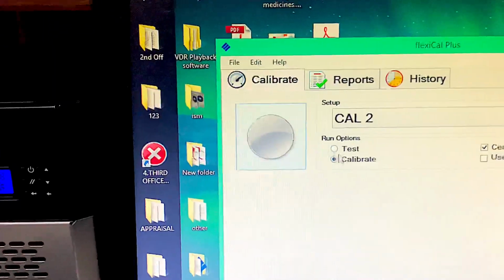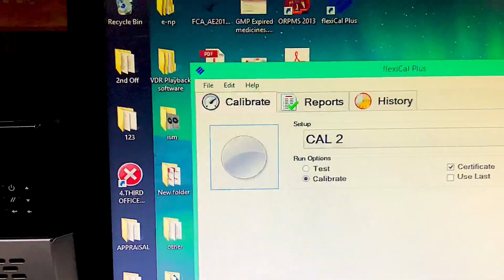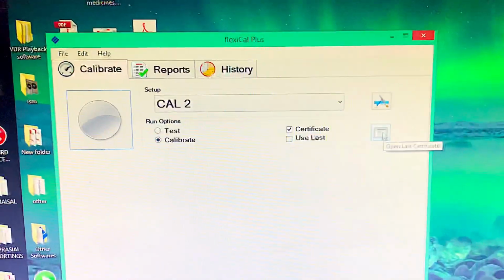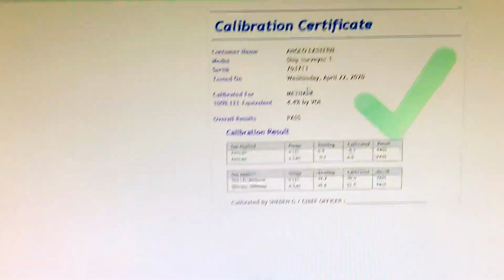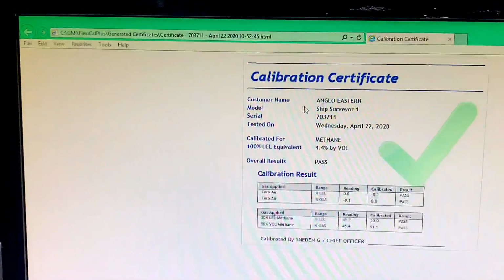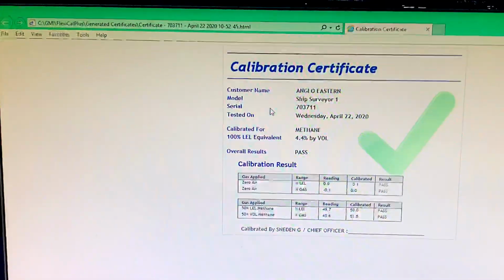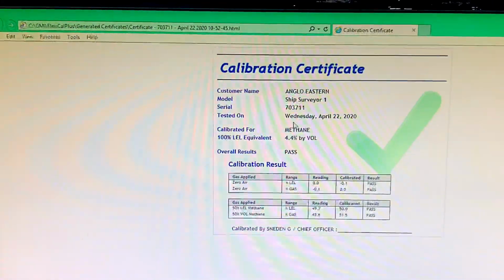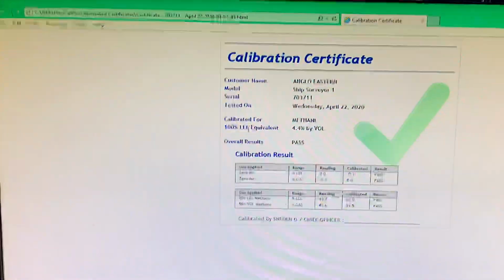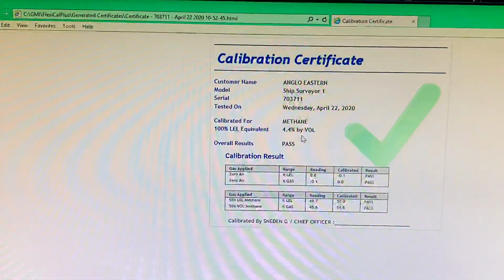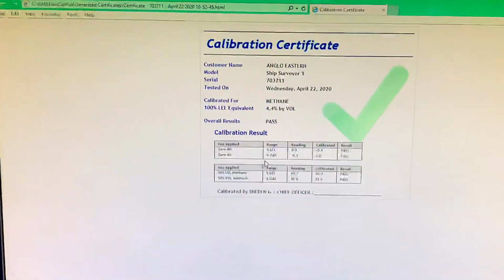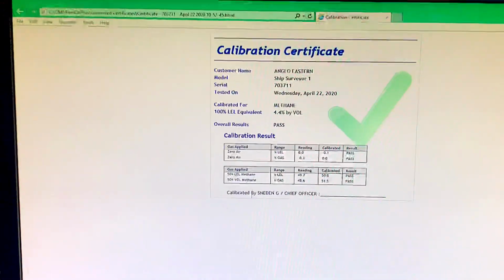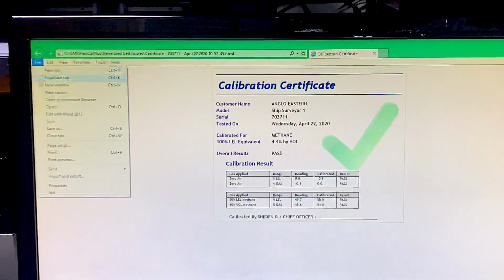Stop. Click on open last certificate. This is how the certificate looks. Customer name Anglo Eastern, model Ship Surveyor 1. It will automatically display the serial number as well. The date 22nd April 2020. Calibrated for methane. Percentage of LEL equivalent 4.4% by volume. Overall results pass. The next step is to take a printout of it and file it.